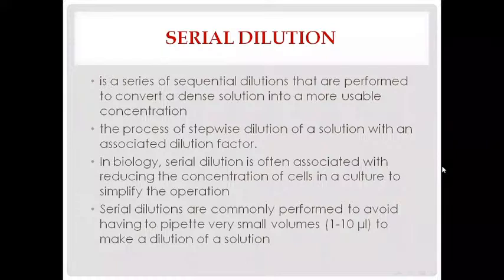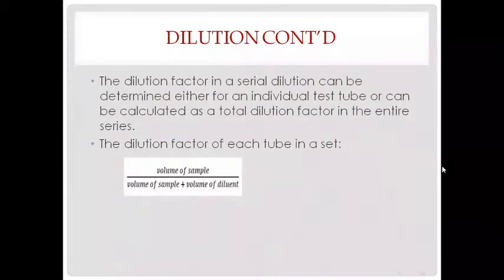So sometimes the accuracy is reduced when you have these small volumes, because there's a lot of interference and it's not very accurate. And if the pipette especially is not regularly calibrated and serviced, you can be assuming to pick 20, 10 microliters or 8, but actually you're picking like 4 or 2, and that has implication on your downstream assay. I think those are the issues regarding the addition.